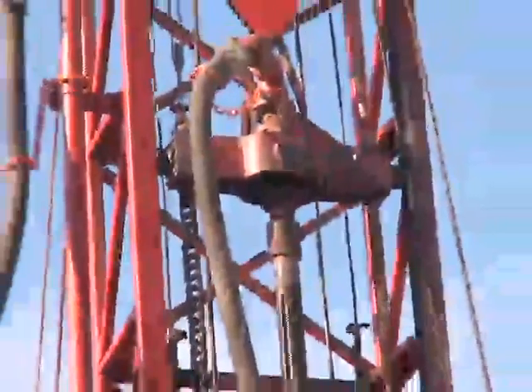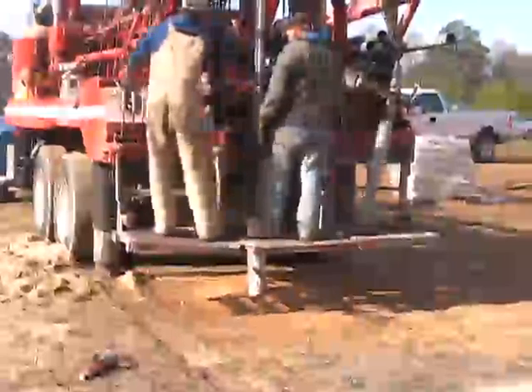The most common medium is the vertical loop. A truck-mounted rotary digging rig is brought to the job site. During setup, the unit is leveled to assure a plumb hole is dug. A 4½ inch wing or cone bit is utilized to start the casing hole. After drilling 4 to 6 feet, the cone bit is removed. Then a PVC pipe casing is pressed into the hole, stabilizing the ground and preventing surface cave-in from occurring.